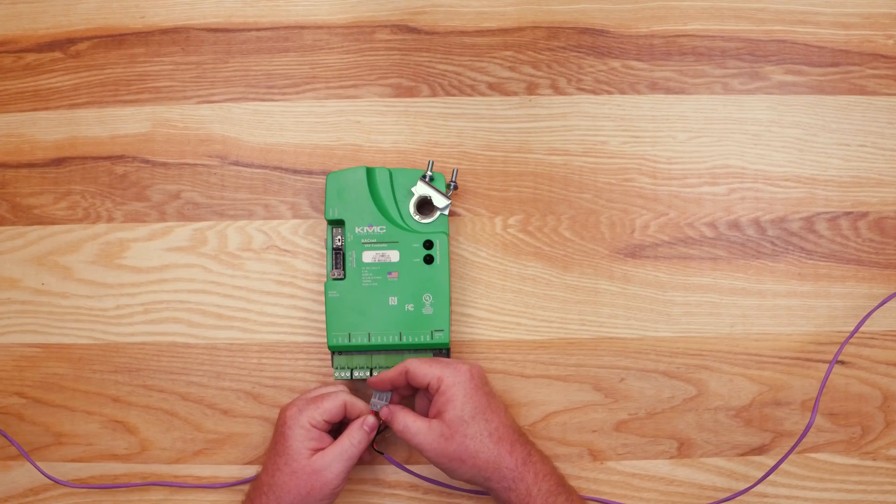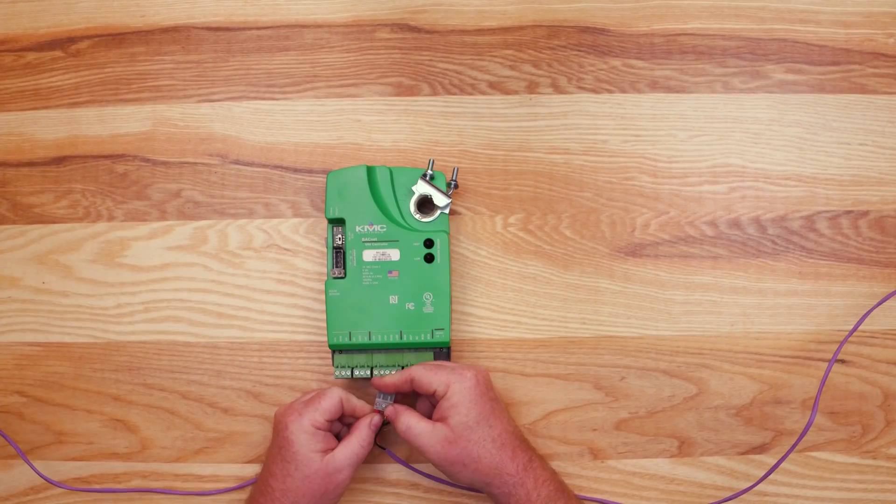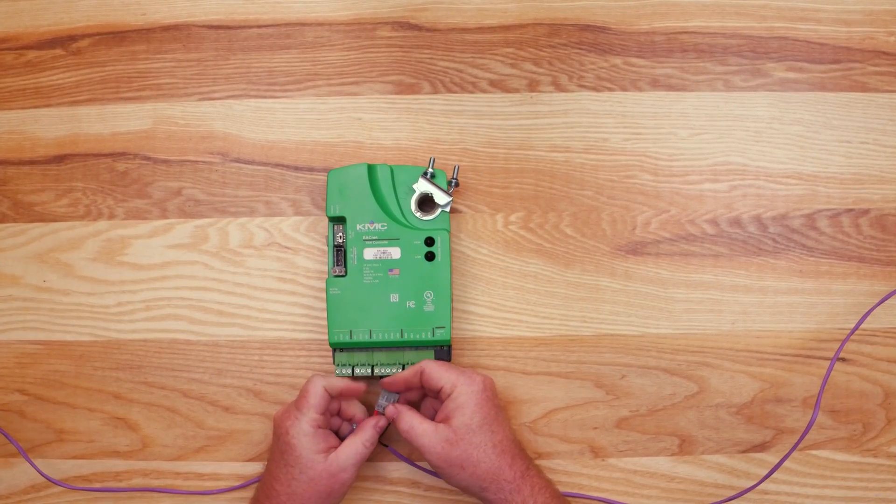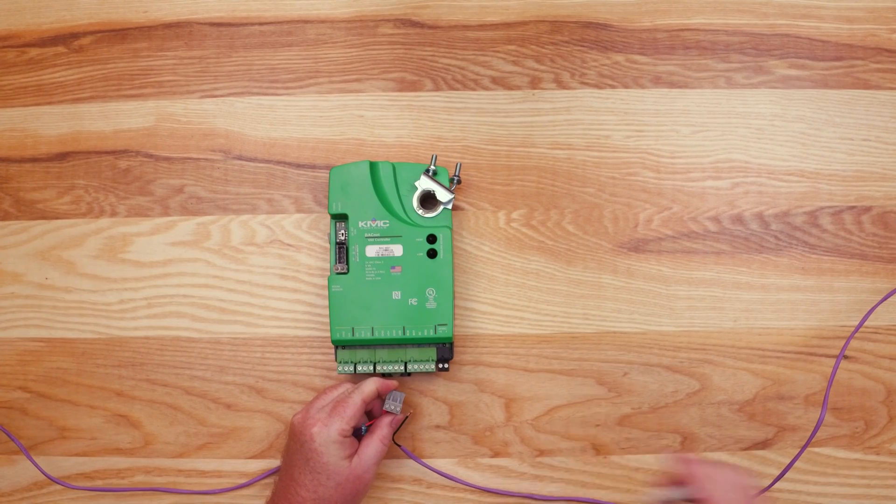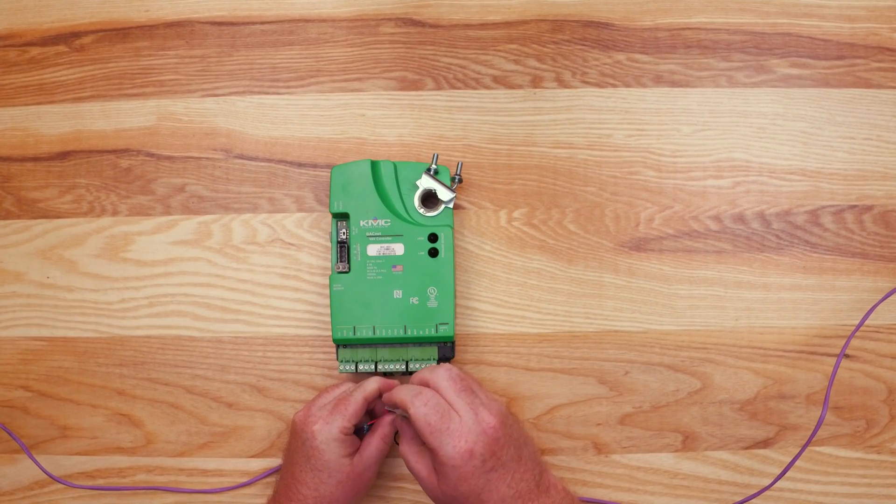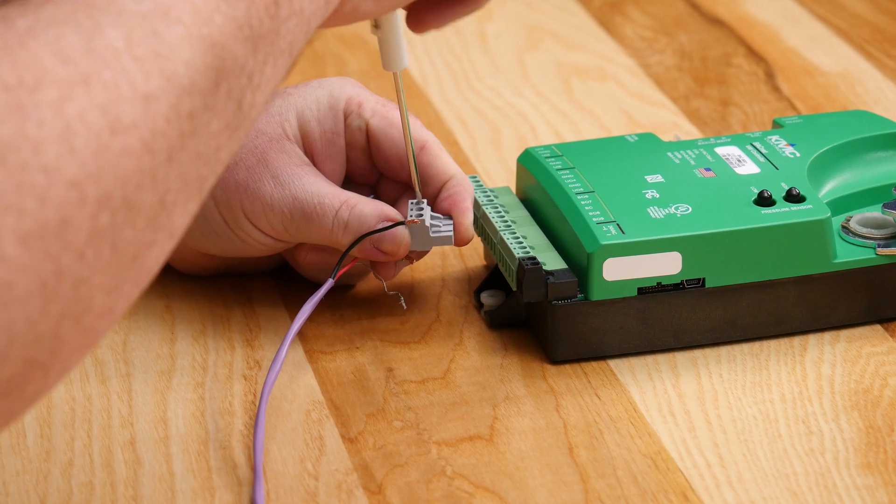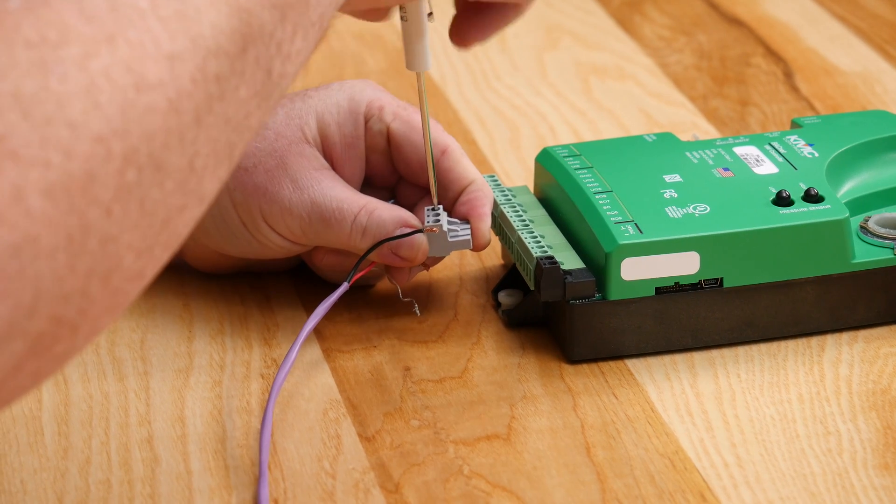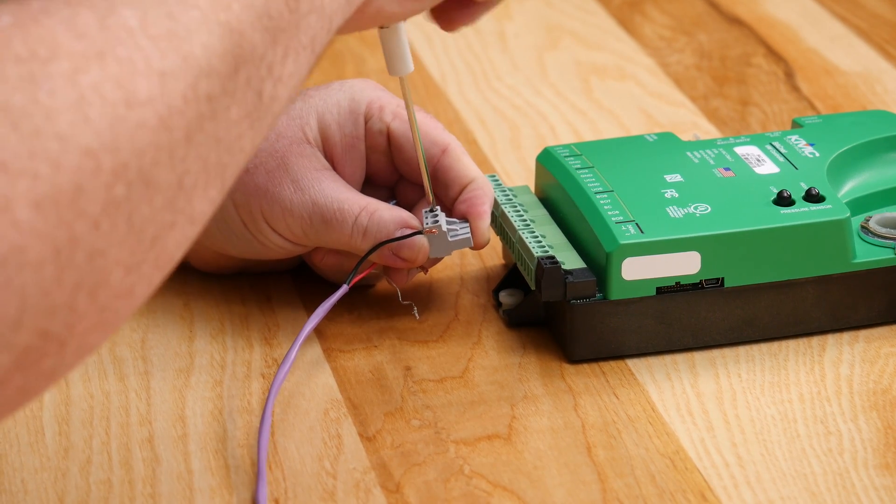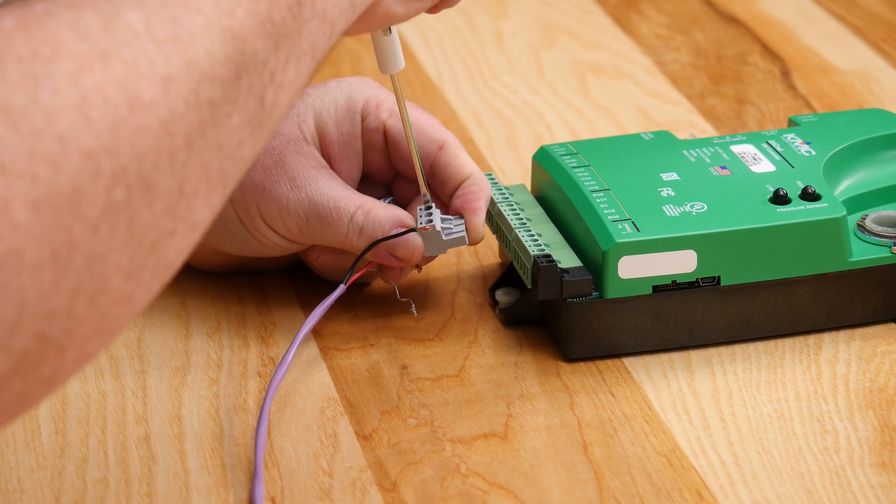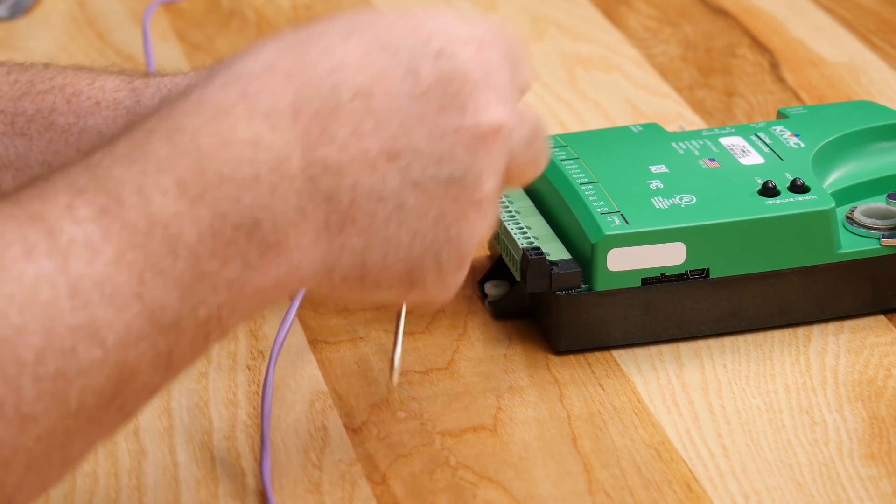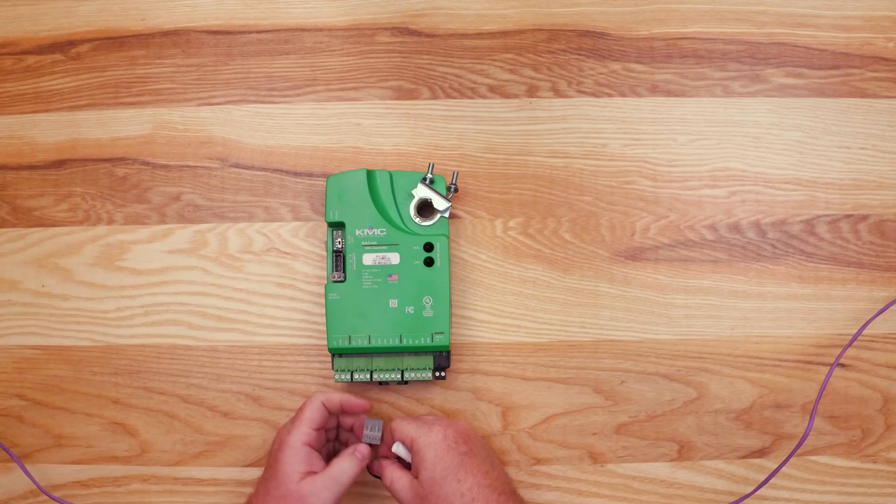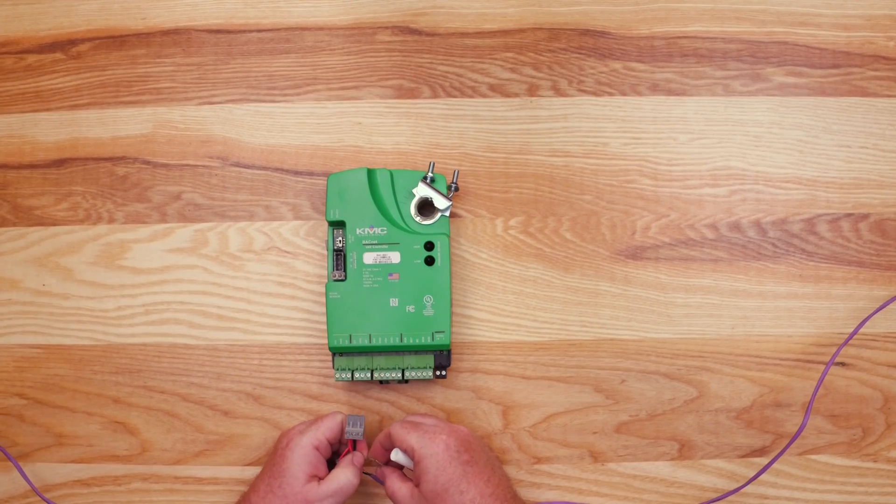Assuming this controller is in the middle of the network, start by connecting the negative A wires in parallel with all other negative A wires on the network. Likewise, connect the positive B wires in parallel with all other positive B wires on the network.